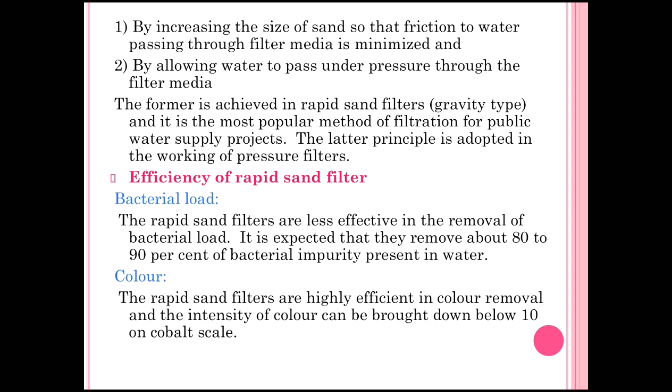Efficiency of rapid sand filter. There are again three parameters. First one is the bacterial load. The rapid sand filters are less effective in the removal of bacterial load. It is expected that they remove about 80 to 90% of bacterial impurity present in water sample.